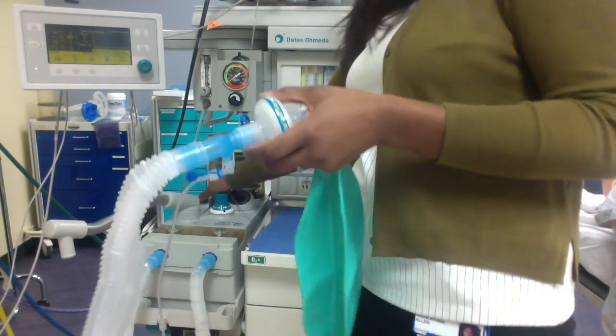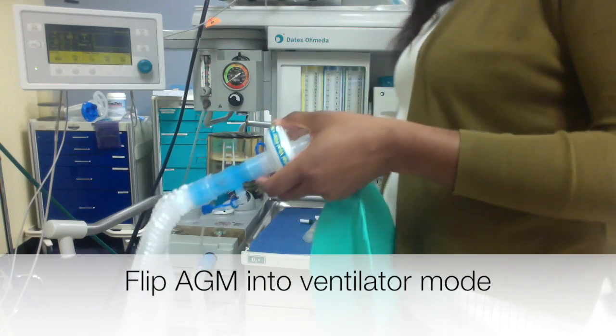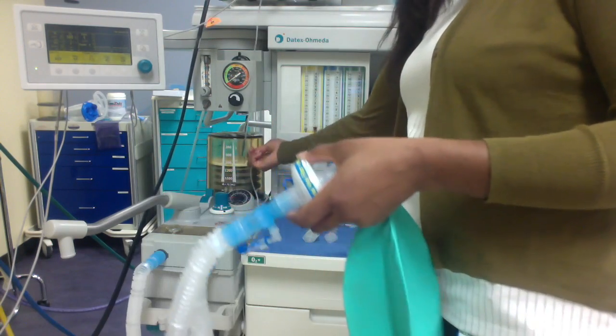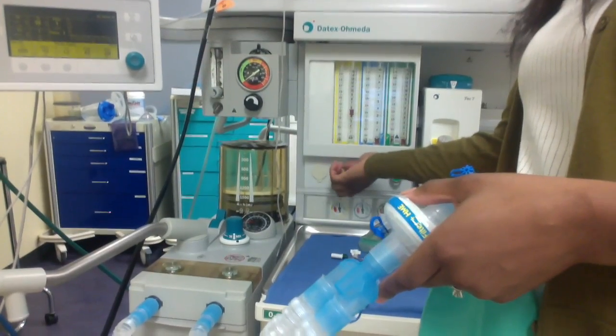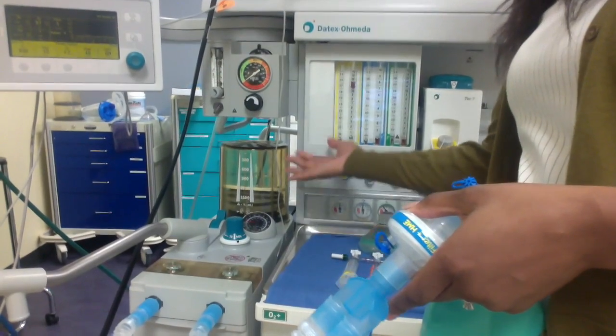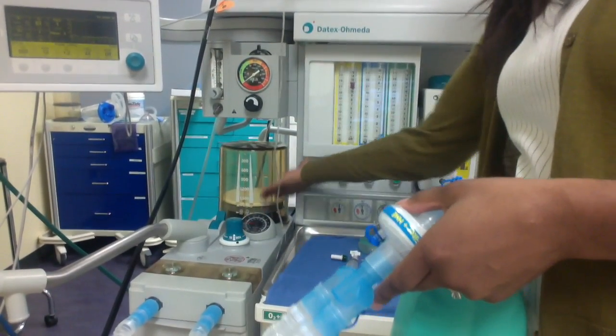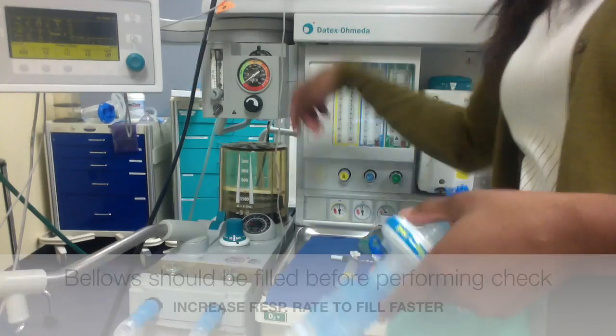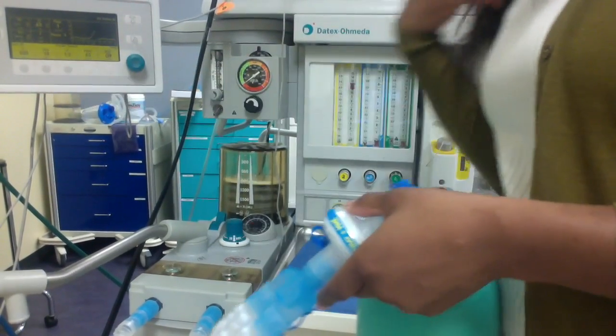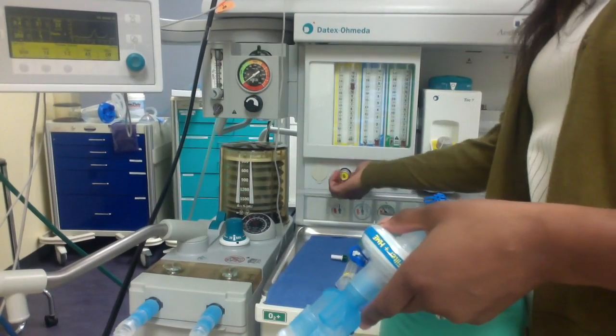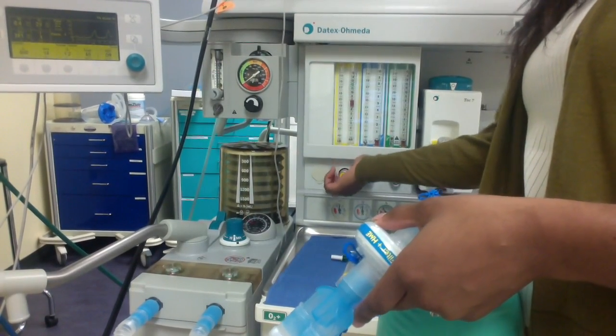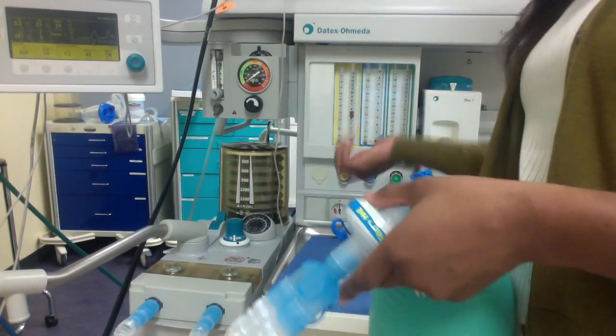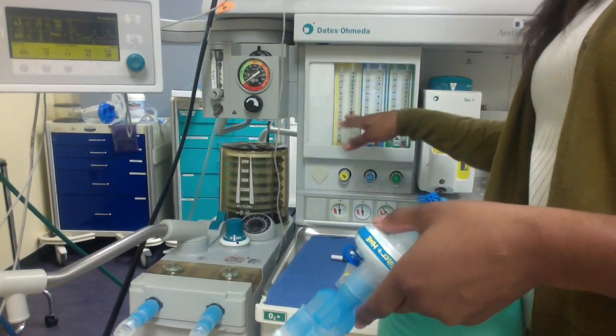I'd flip my ventilator on to ventilator mode, and what will happen is these bellows will start to rise and fall. I'll turn up some air, and I want to make sure, before I start my complete check, these bellows need to rise all the way to the top. So I'll turn my rate up to facilitate that and make that go a little bit faster. So they're at the top, and so when I'm checking the ventilator, I want to check it at flows that I would actually deliver to a patient. So I'll start with 5.